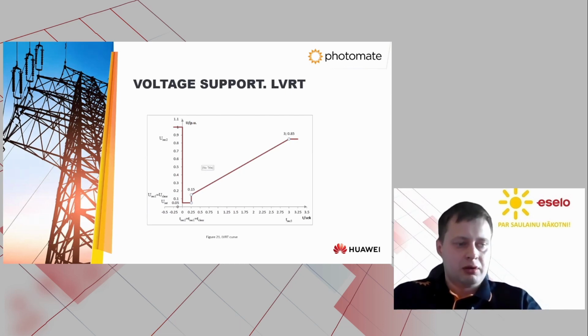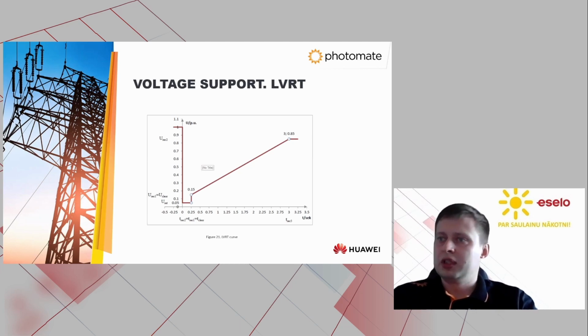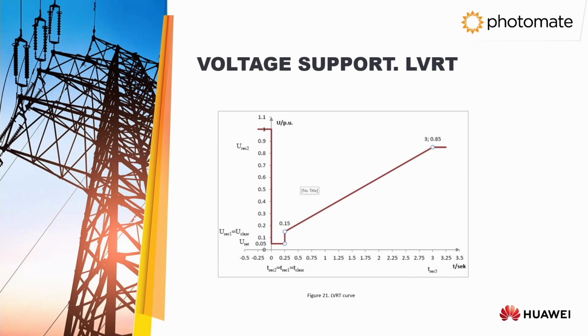Another function, which is mainly requested by various distribution system operators, is called LVRT, low voltage ride through. This feature is often used because if the voltage drops for a very short time, the inverter must stay connected to the grid. If it is disconnected, it will make the problem worse. So the inverter stays connected to support the grid. Usually this is a problem when the grid experiences short circuits. At this time, if the voltage drop falls within the curve shown, the inverter tries to support the grid with reactive power and stays connected.